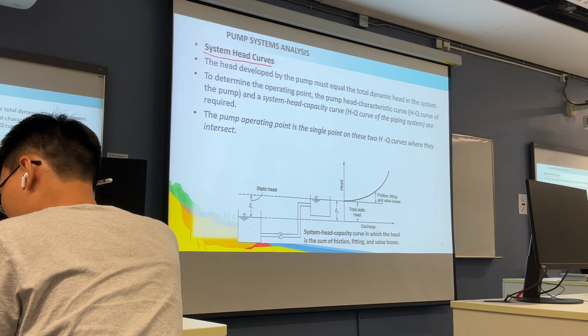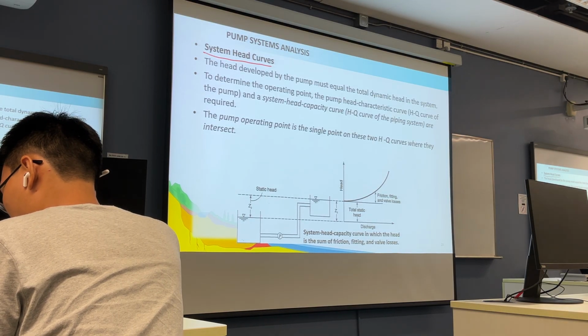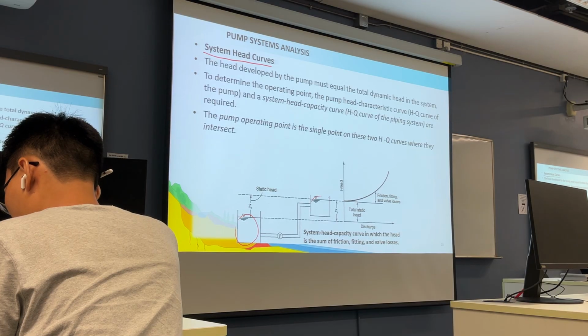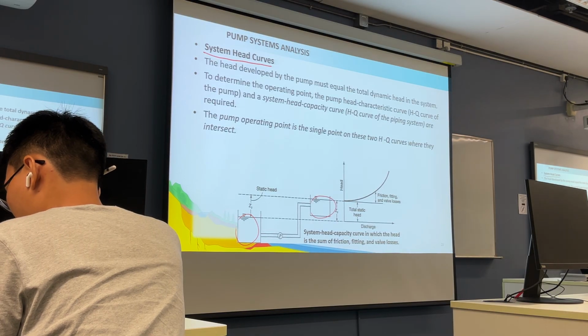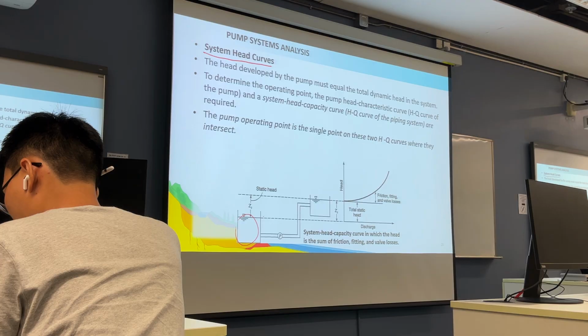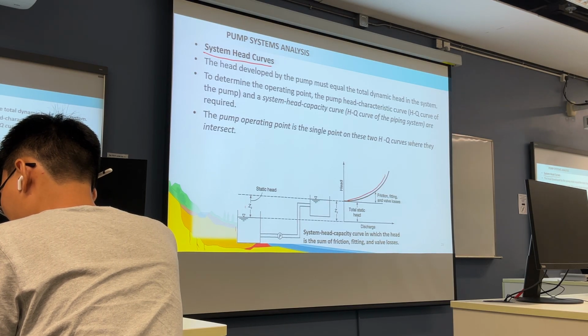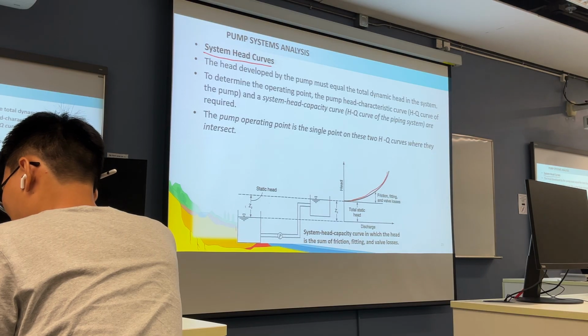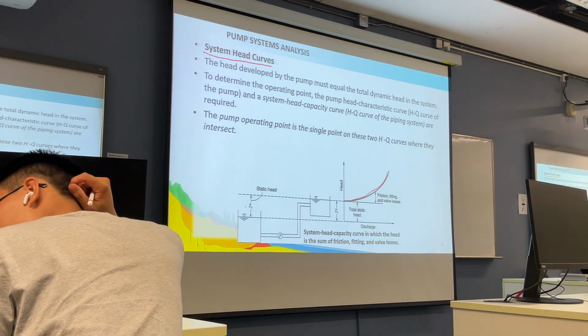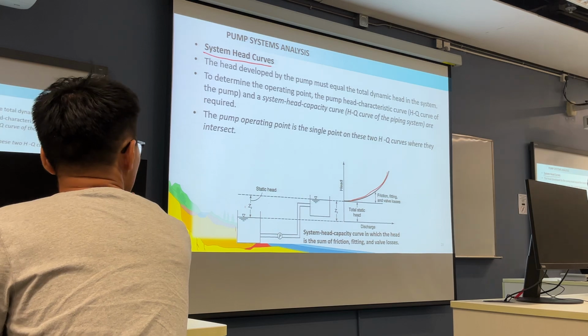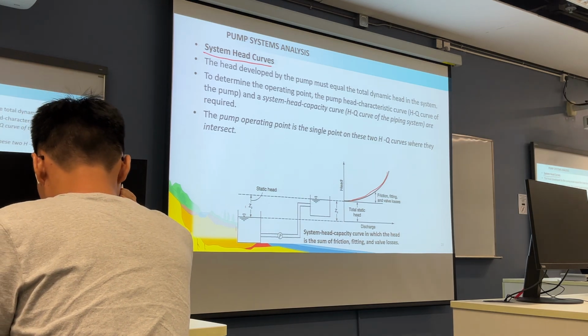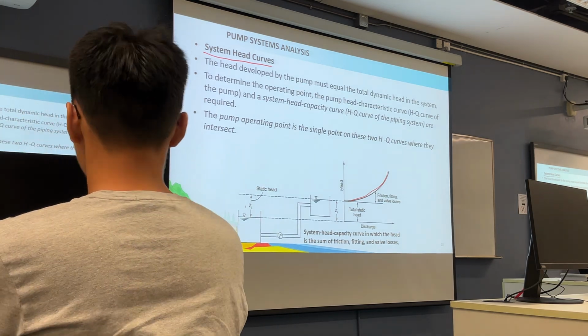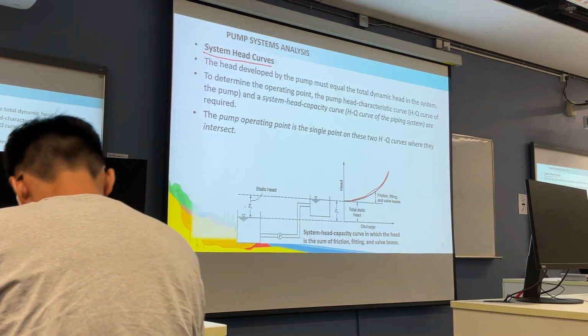For example, if we would like to deliver water from the lower reservoir to the higher reservoir, at least we need to overcome the elevation, so it will be a curve like this. It will be a proportional curve, other than the pump curve, okay. So it indicates that if you want to pump water at a larger discharge, you need to provide more pump head, okay.